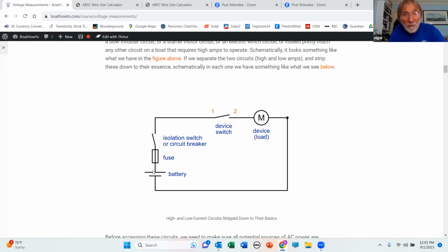Now, in a perfect world, this is a single piece of wire with all the switches and fuses closed. In a perfect world, we'd read 0 volts because it's just like we put the 2 meter probes on the same battery post. So whatever we read here, maybe we read 3 volts, is voltage drop in that side of the circuit. And then we can start working our way back, taking readings. If we get a uniform reduction in voltage readings as we go back along the length of this conductor and through all the bits and pieces of kit, then the conductor is undersized. It's causing the voltage drop.